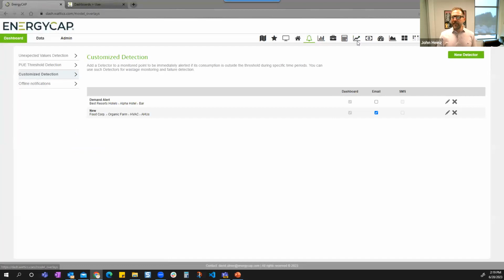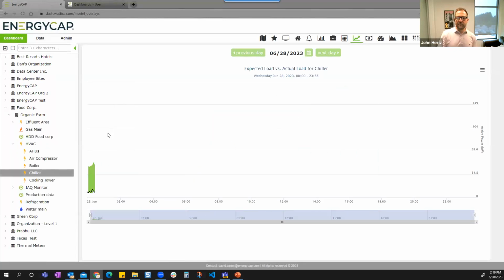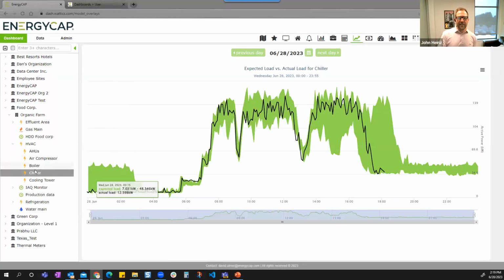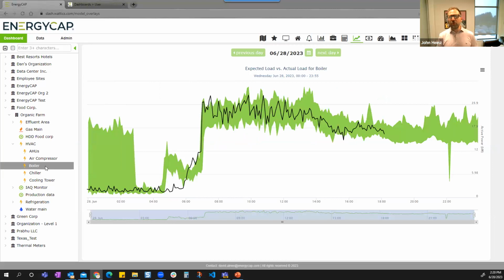Another capability the system provides is a view called Sentinel. Sentinel leverages machine learning to say, for this chiller, what is the expected profile based on historical usage, weather impacts, and other factors? What is the expected behavior of a piece of machinery, a zone in a building, or a production line? The green is what's expected and the black is the actual, creating this profile for every point. You can see here the boiler didn't turn on when it normally does.